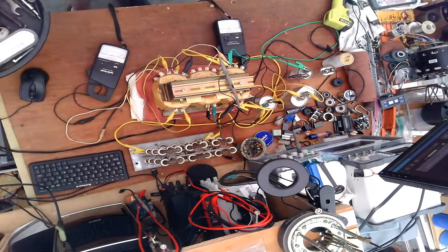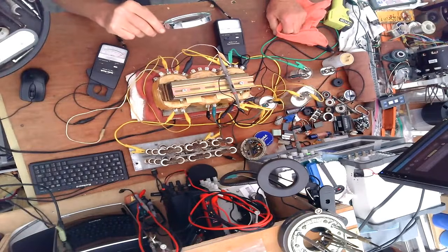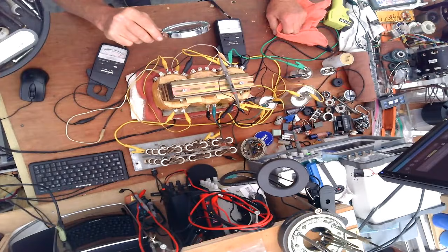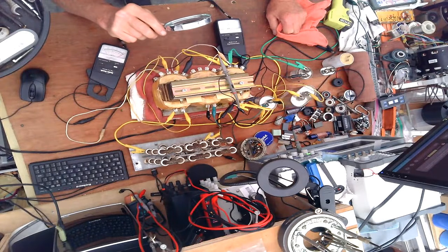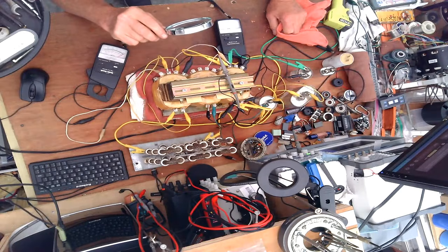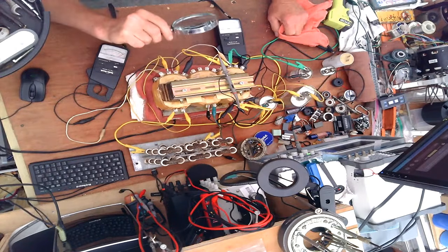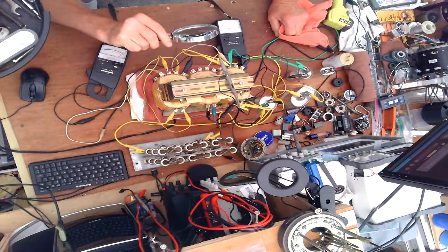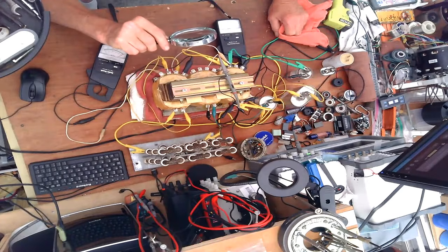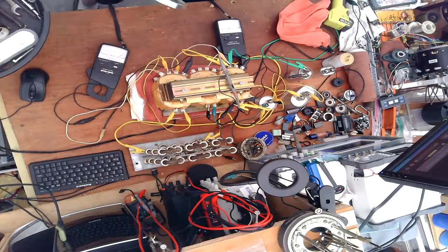I can't do a snapshot, but this is a Schindler Elevator Corporation unit, part number 222981, rated for 165 VA. Ultimately this is a step down, either 208 or 480 on the primary side, and the secondary side is 100 volts.